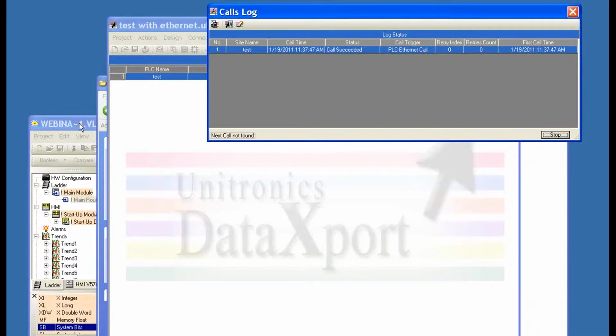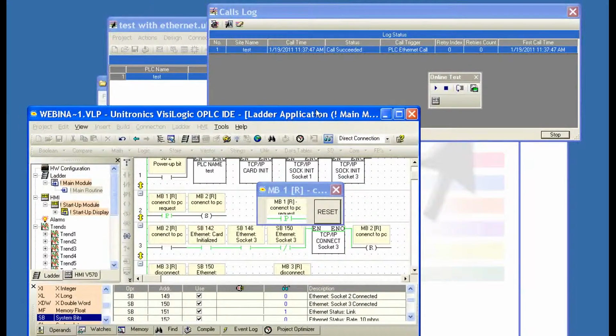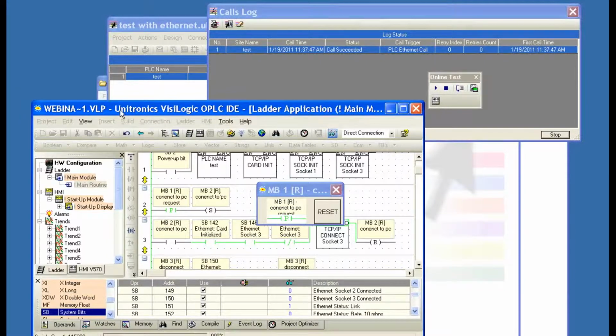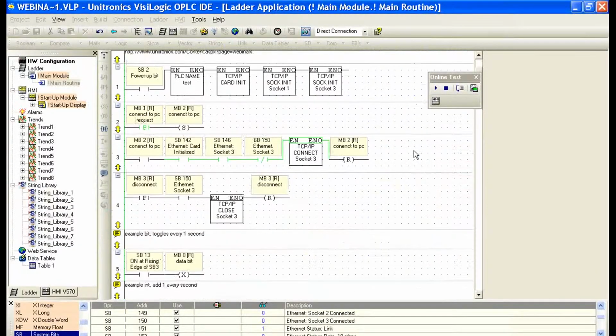Now, again, I have to stress how important this idea is. If you wish to have the PLC initiate the data table download, this is how we do it. And if we want to get away from a time-based event to an event-based event, we need to use this. We can use TCP over GPRS, of course. We can do it over the wireless cellular network, or over the internet. We can have the PLC across the country or across the world. It's going to be the same. So this is a very powerful option.